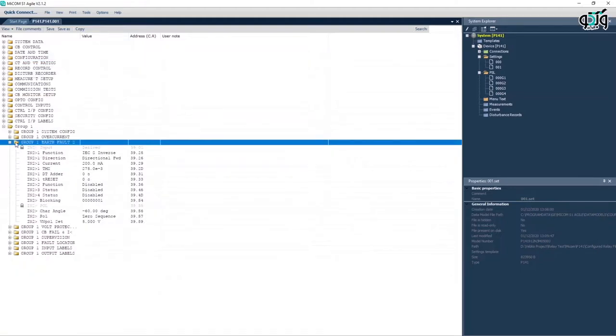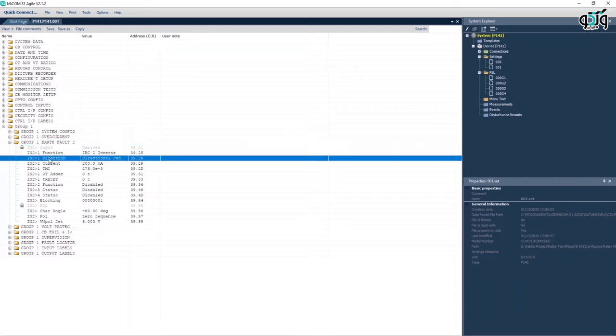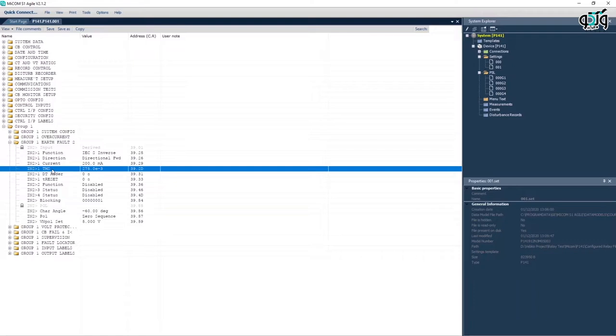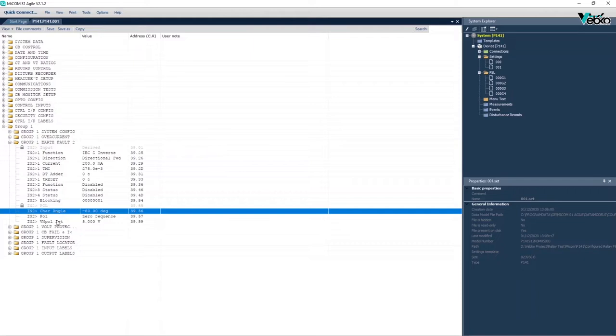In settings section, the activation state of this element is indicated by a standard inverse curve in forward direction while the 200mA setting is indicated by 0.275 TMS. Also, a minus 60 degree characteristic angle is considered. In the end the polarization voltage threshold is recorded to be 6V.